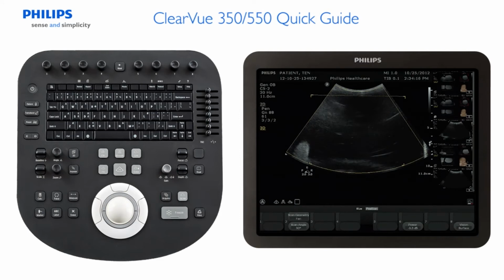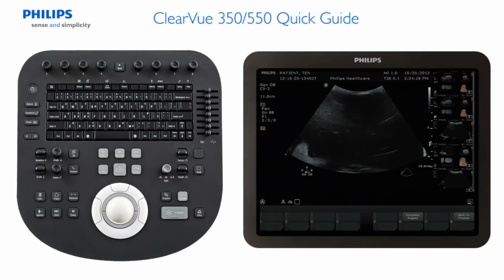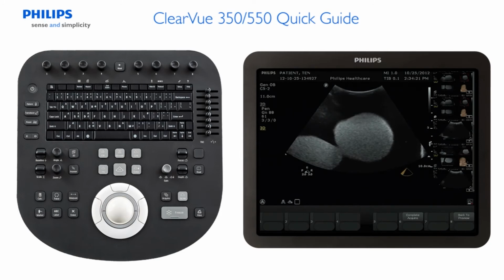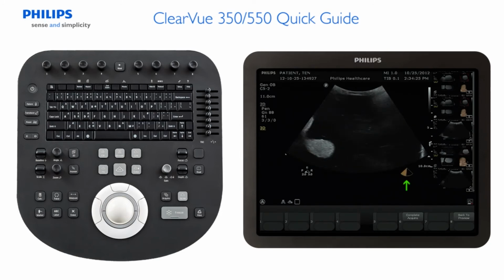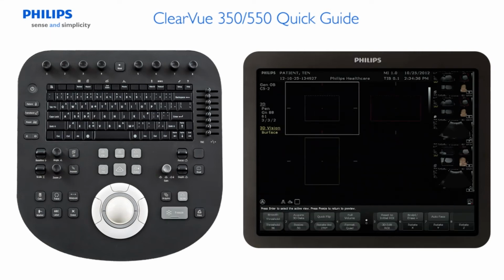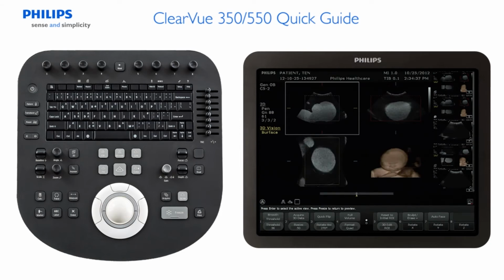Press Acquire and fan the transducer in a steady continuous sweep across the area of interest so that the acquisition sweep is in time with the timing bar located in the lower right portion of the display. To end the acquisition, press Freeze. The sweep must be completed before the timing bar reaches the end.